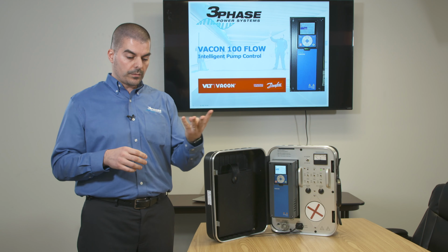Let's imagine we're controlling pressure in a pipe. When we start the drive, we could tell the drive to slowly fill the pipes. So we have a mode inside called soft fill. We have another capability that we're going to go through at training time. We can detect if the pipe is leaking. For example, if we're pumping water in a pipe and there are leaks, we can detect when that happens and we can alert and alarm the owner or the operator of the drive very, very easily.